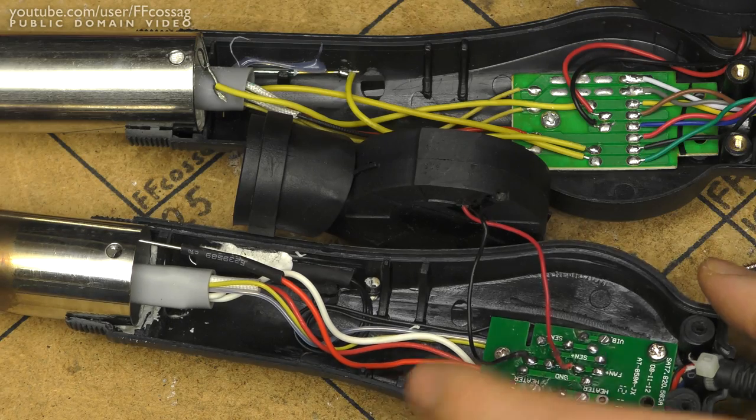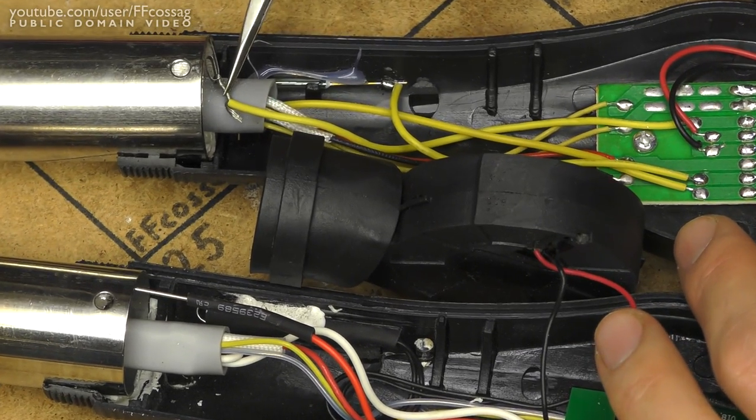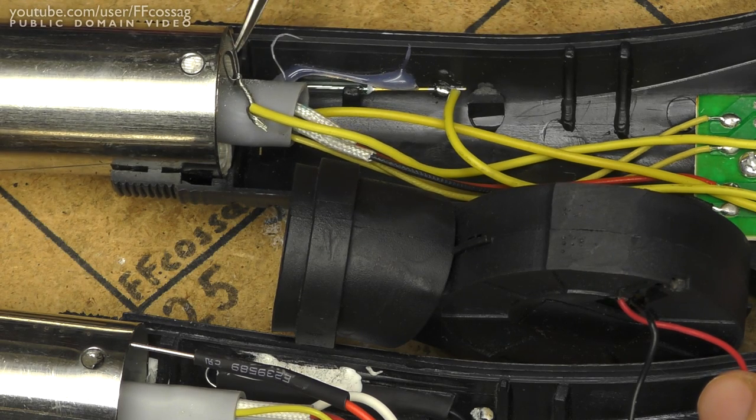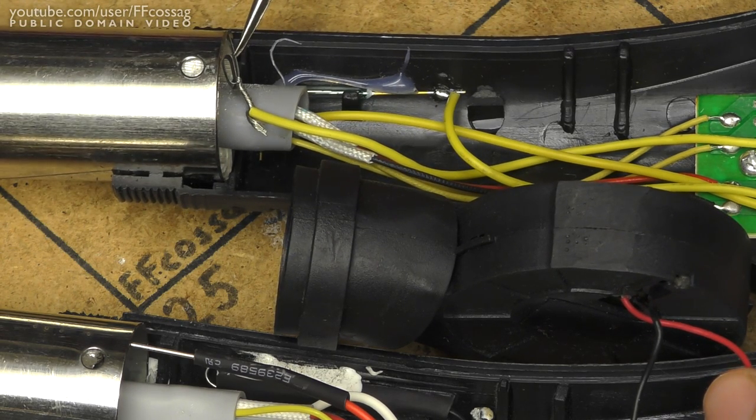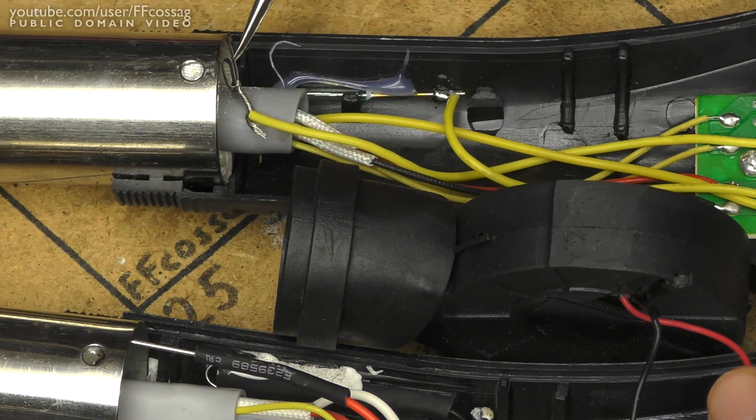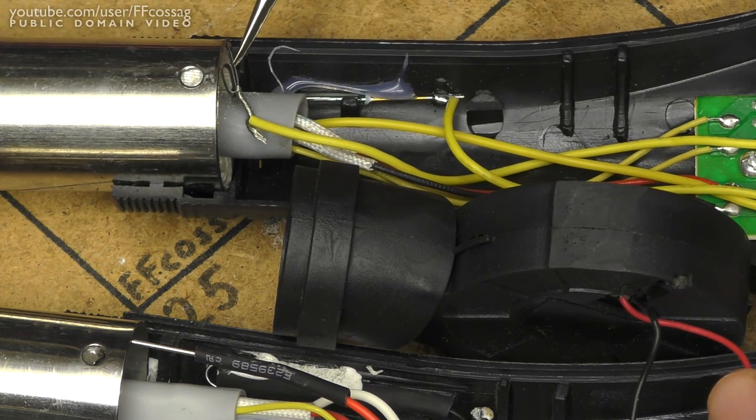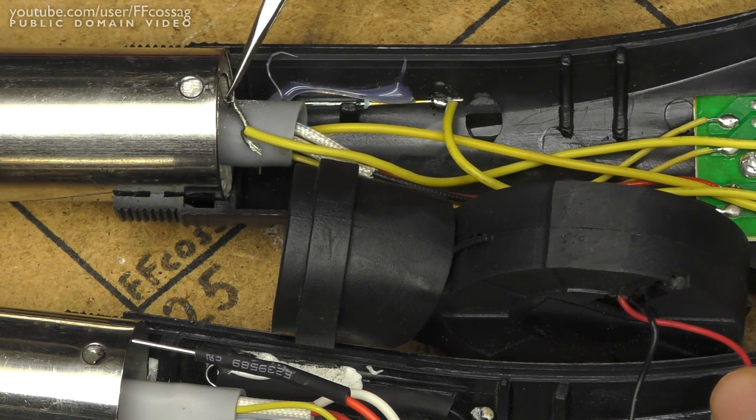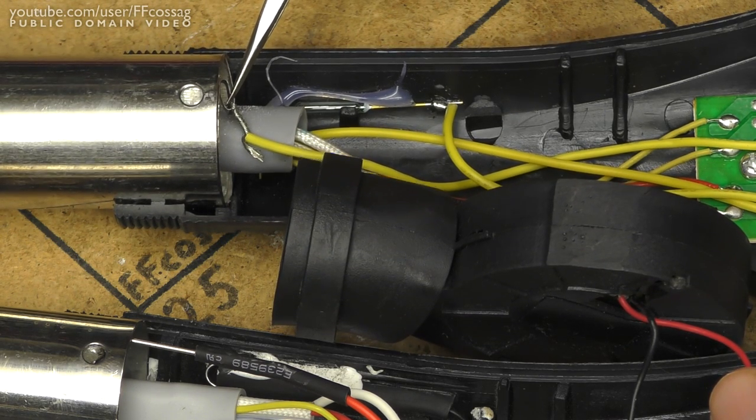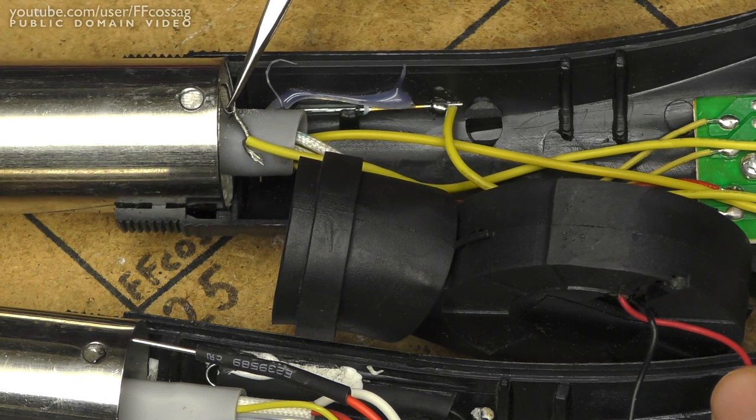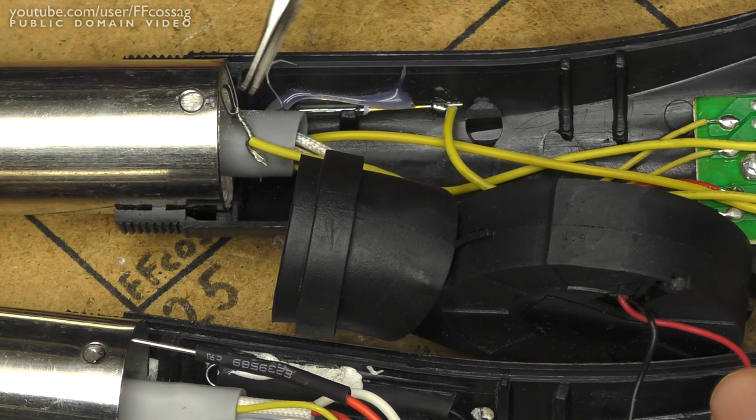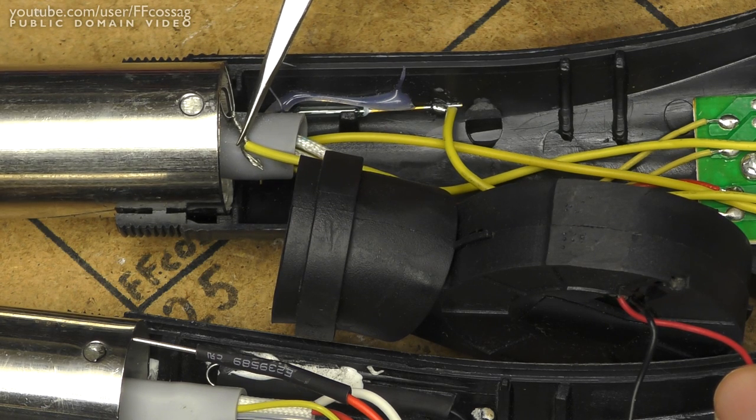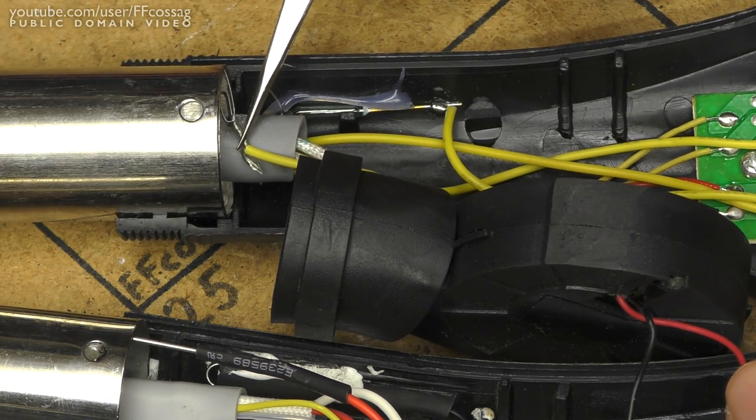On the new one, they've just got a wire wrapped around a piece of metal welded to the outer cover of the heater. It is going to make a connection, but that is not very reliable, especially as this moves, the unit ages and thermally expands and contracts. This is not going to provide a secure ground connection, and assuredly no safety agency would ever approve of this.